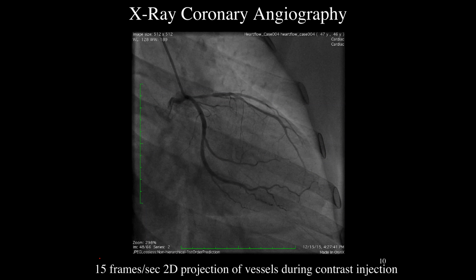Here, you have to ask yourself, what's image quality in this instance? What are we interested in? We're interested in detecting that vascular abnormality, that thing right there. So we need the spatial resolution to resolve where it is, and to ask what's the dimension of the vessel when it's thinned down. We need the grayscale level to be measurable with a good signal to noise so that we see that there's a reduction in attenuation at this point.